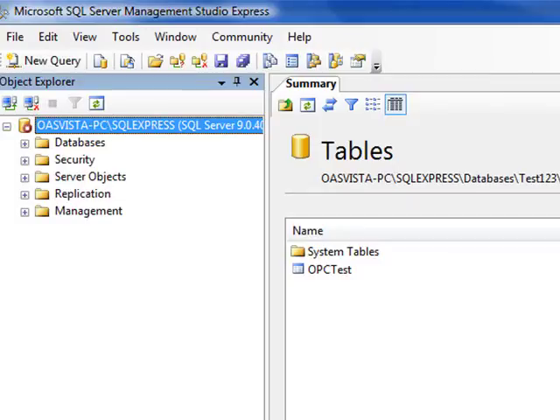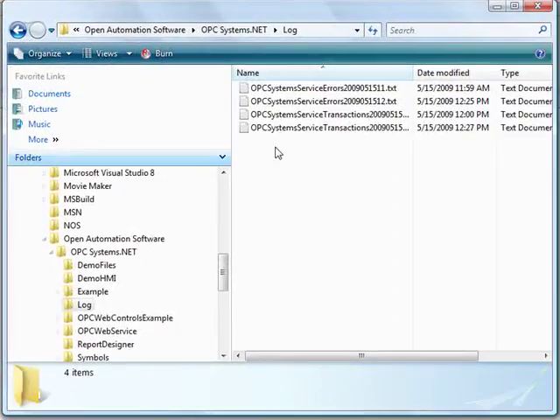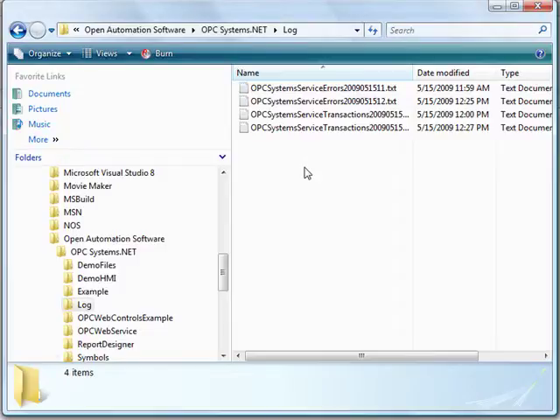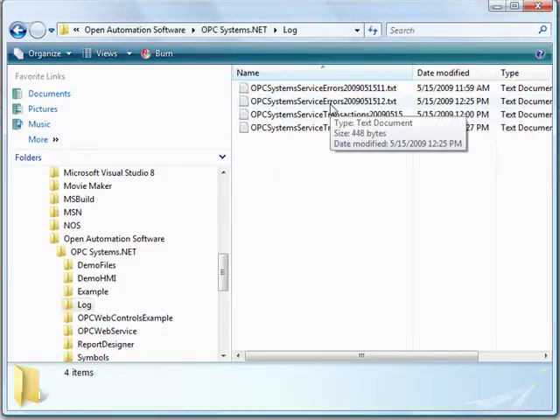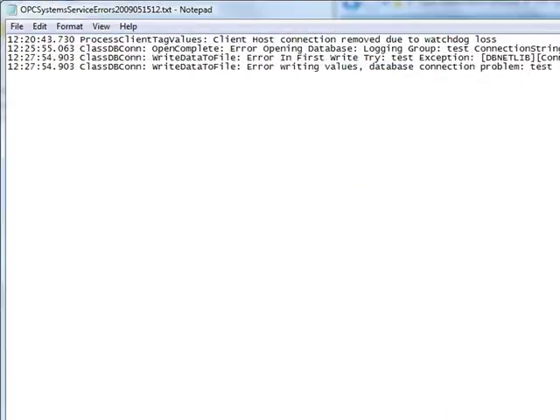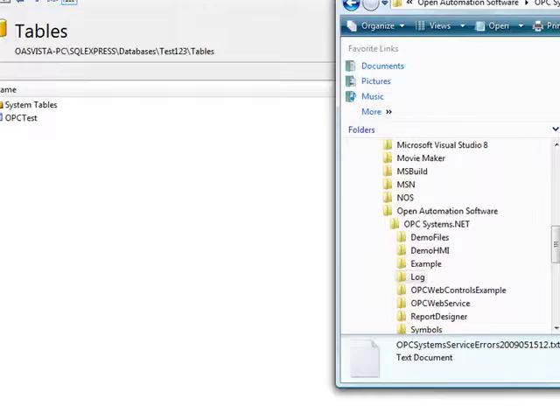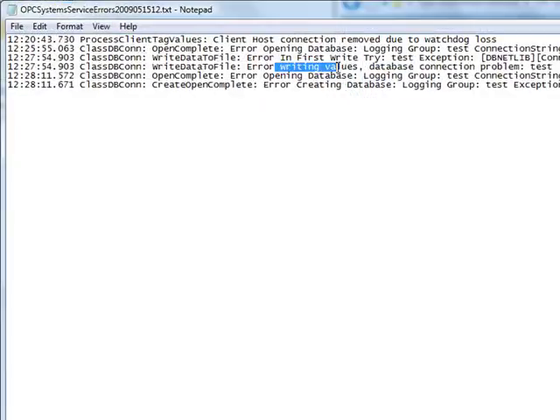If we now return to the error log directory, where the OPC system's errors are being recorded, and double-click on the latest error log, we see that we have errors indicating that we have a first write failure, with an exception that the connection problem to the database. If we close the error log and open it again, we'll see we have further errors of not being able to open the database. This could be related to a security problem in the SQL Server engine, which I'll show you how to overcome in just a moment.